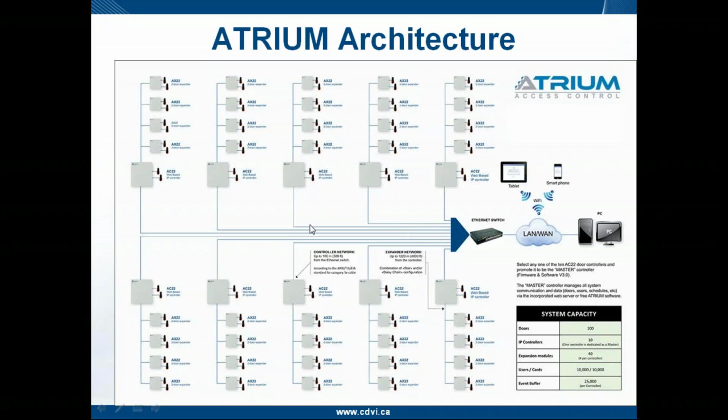So there's a complete copy of the database on each subcontroller. If the subcontroller does go offline, it continues functioning, the schedules continue functioning, the access levels, the cards, and of course the connected expanders on that will continue functioning as they always do.